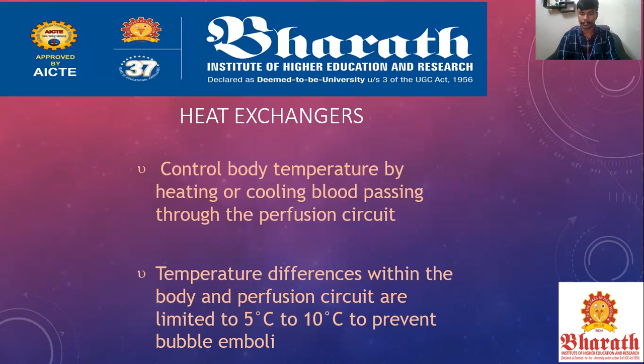The temperature difference between the body and the perfusion circuit connected with the body will be limited to 5 to 10 degrees Celsius to prevent bubble embolism. Why? Because during the purification, that means during the conversion of deoxygenated blood into oxygenated blood, there will be a variation in temperature which will be visible and notable. So it will vary by 5 to 10 degrees Celsius when the blood is purified, that is, when deoxygenated blood is converted into oxygenated blood in the heart-lung machine.